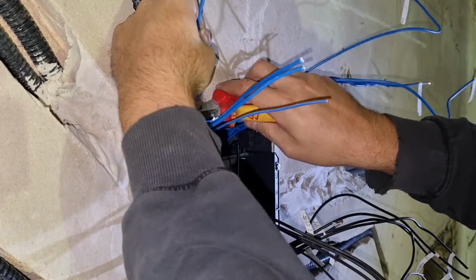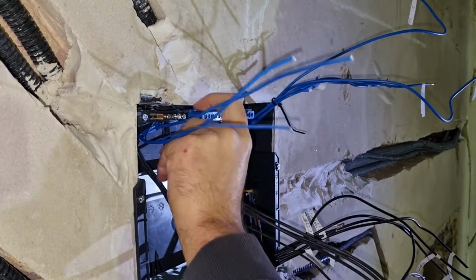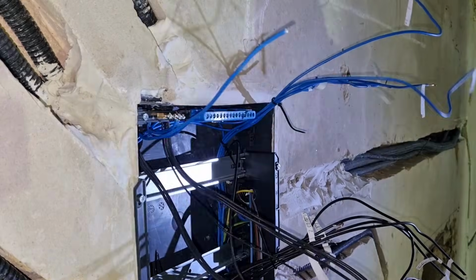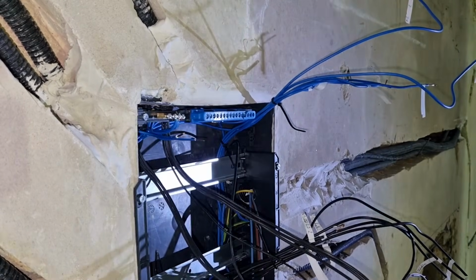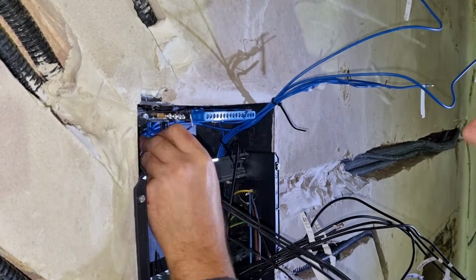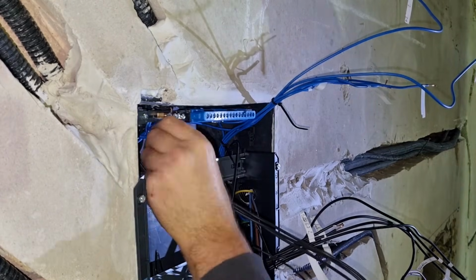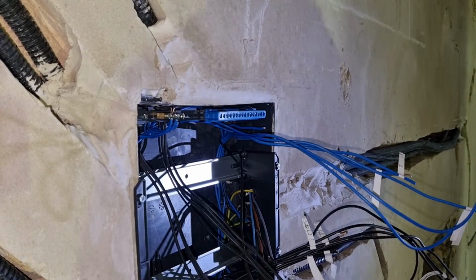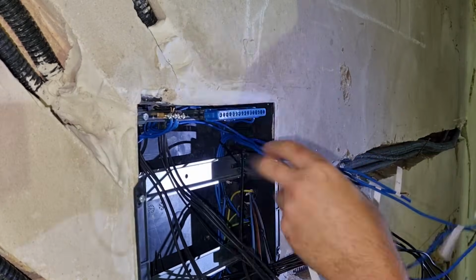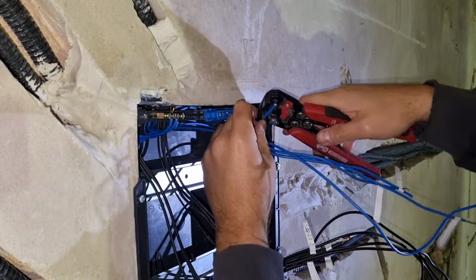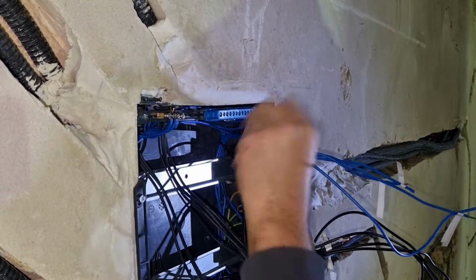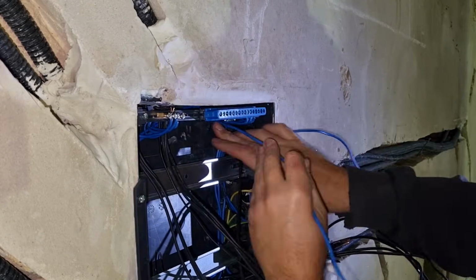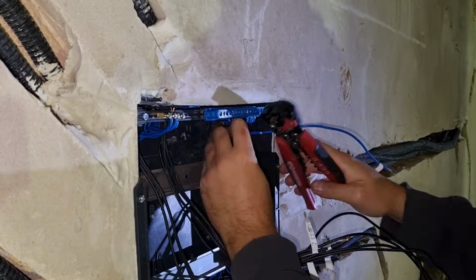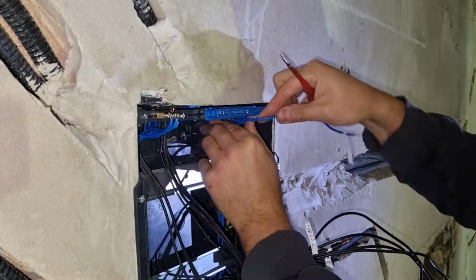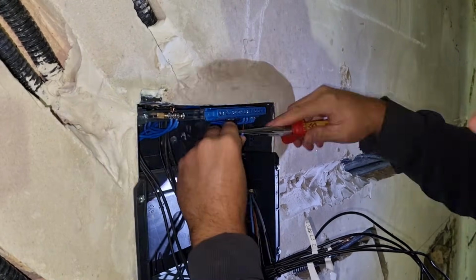A key difference with this board is that because of the 2 live protection relays, we also need 2 separate neutral wires. Building this main distribution board took about 4 hours. Here too, everything runs from B13 miniature circuit breakers except the 3-phase circuits, which run from 3 by C13, and the lighting, which is on B6.